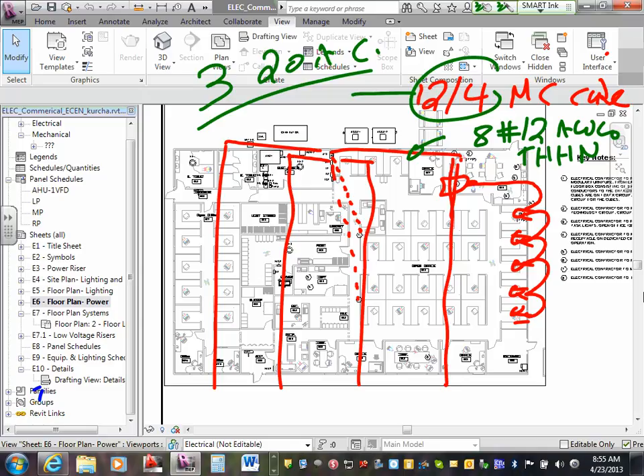Any comments? Group them together either with multi-wire branch circuits, or if you don't want to use multi-wire branch circuits, then in this case you're going to be using more cables. You're going to use a 12-2 or 12-3. You're going to be using a lot of 12-2 to loop them all together. Any comments, guys? Any questions? Good point, though. Any comments? Any questions?